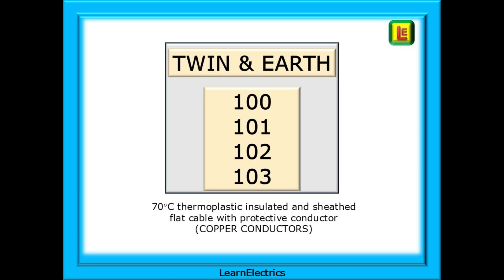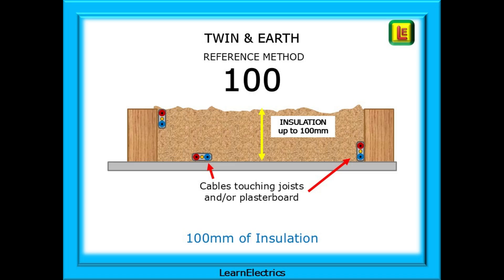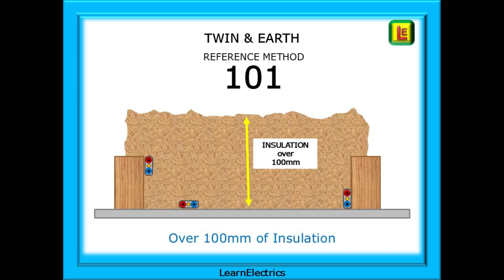Now for the methods specific to twin and earth cables - the hundreds. We know it as twin and earth, but the wiring regs call it 70 degrees Celsius thermoplastic insulated and sheathed flat cable with protective conductor, copper conductors. The first one is reference method 100, and I remember this because the insulation is up to 100 millimetres in thickness. The cables are touching either the joists, the plasterboard, or both. For reference method 101, think 101 is more than 100, so the insulation must be more than 100 millimetres in thickness. The cables are still touching the joists and/or the plasterboard, so 101 is over 100.